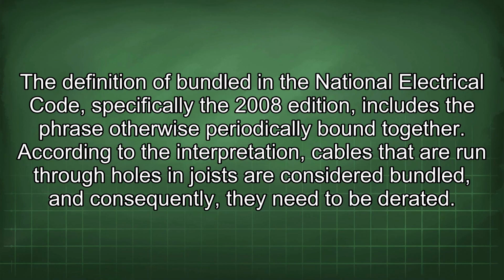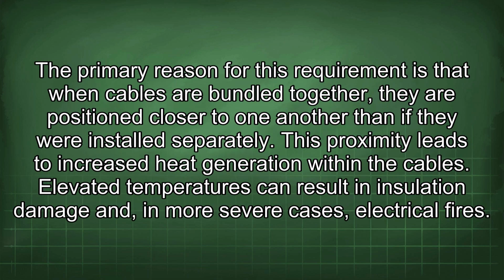The definition of bundled in the National Electrical Code, specifically the 2008 edition, includes the phrase "otherwise periodically bound together." According to the interpretation, cables that are run through holes in joists are considered bundled, and consequently, they need to be derated. The primary reason for this requirement is that when cables are bundled together, they are positioned closer to one another than if they were installed separately. This proximity leads to increased heat generation within the cables. Elevated temperatures can result in insulation damage and, in more severe cases, electrical fires.